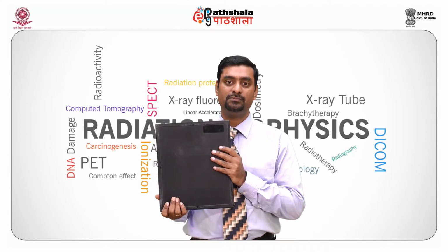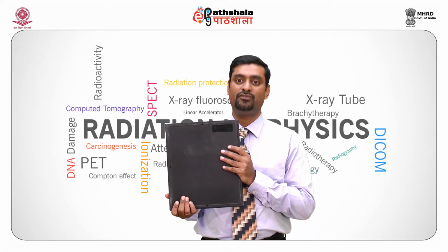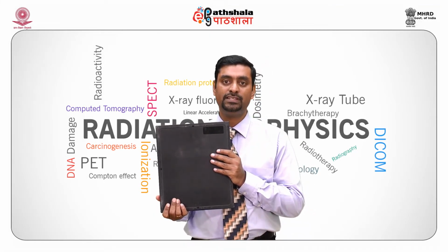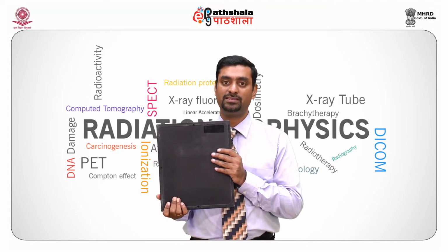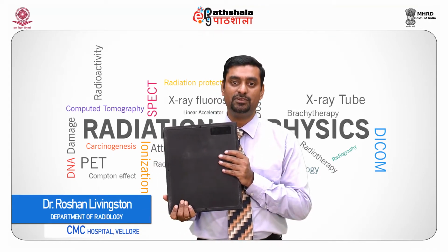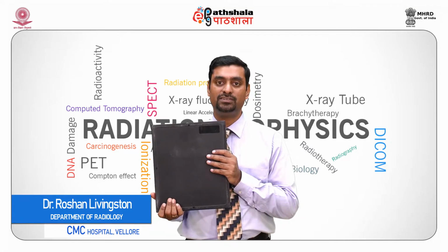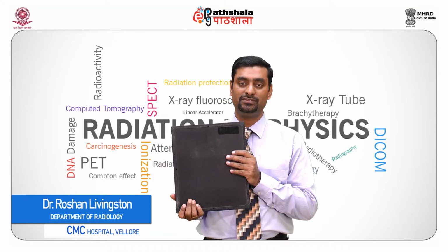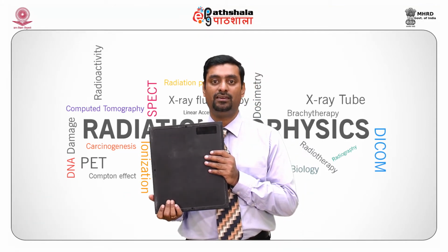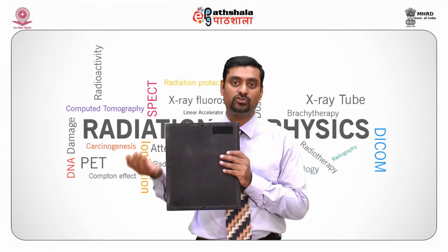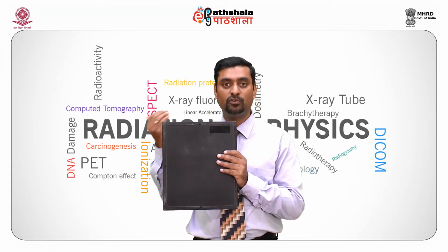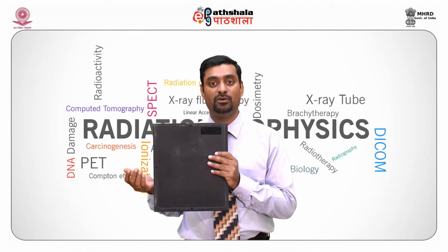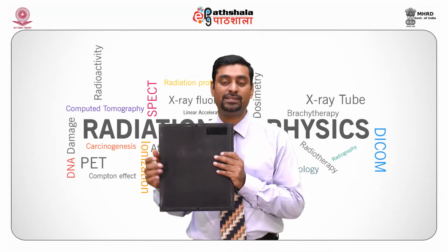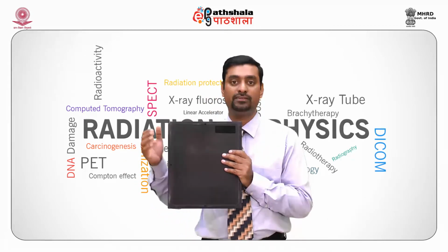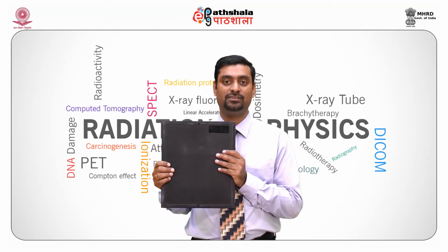The detector is made out of photostimulable phosphor plate. These phosphors, once they are hit by X-rays, form a latent image. The latent image is an invisible image. When struck by a source of light, which is photostimulable, it will produce energy in the form of light. That light we need to take and convert into electrons as photoelectrons and form an image.